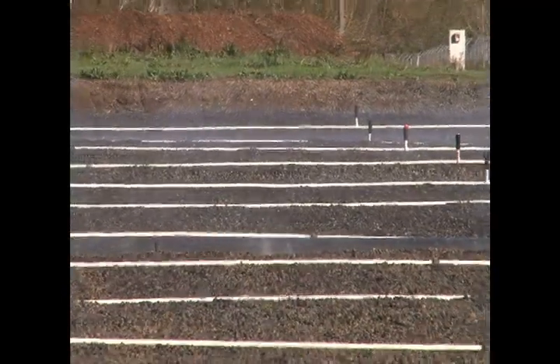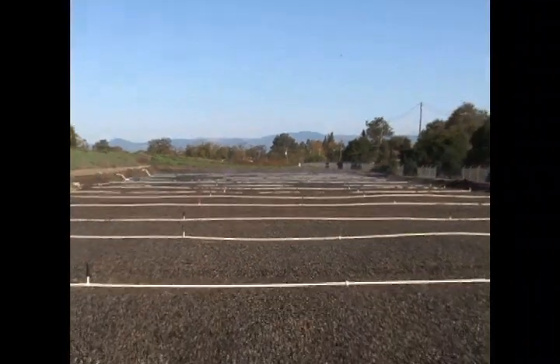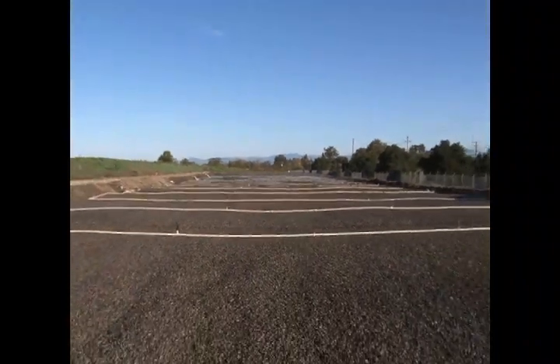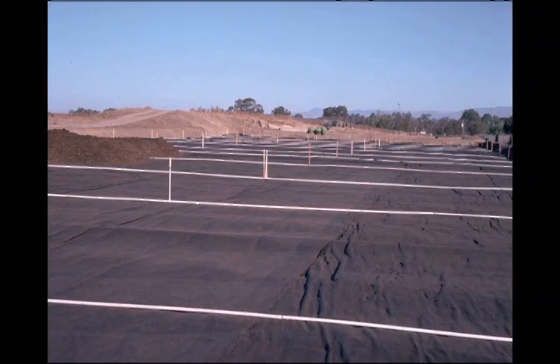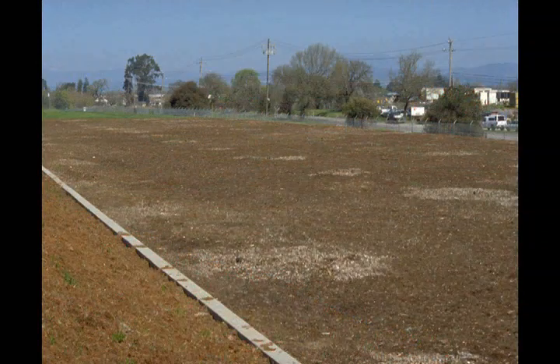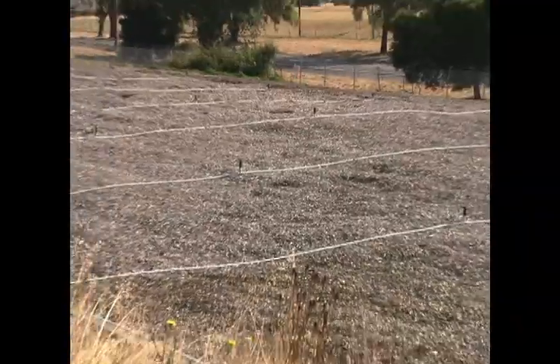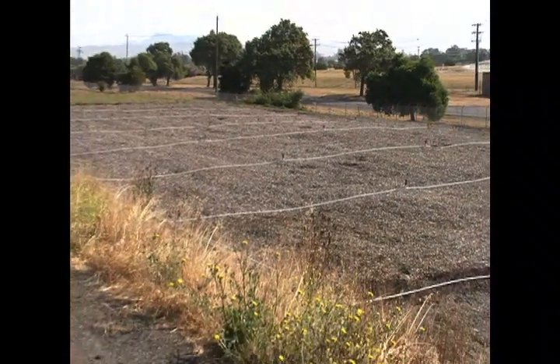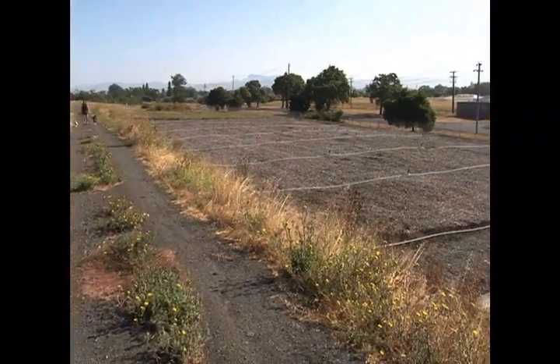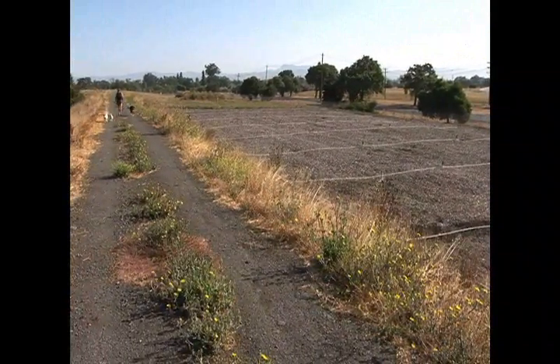The biofilter is an innovative, environmentally friendly biological air treatment system that replaces conventional chemical air scrubbing units. The air is introduced into the biofilter through perforated pipes at the bottom of the bed. As it travels upward, it is evenly distributed through a layer of gravel and then progresses through a three-foot layer of a variety of media. Living organisms in the media consume ammonia and other odorous compounds, scrubbing and polishing the air by the time it reaches the surface in less than three minutes.